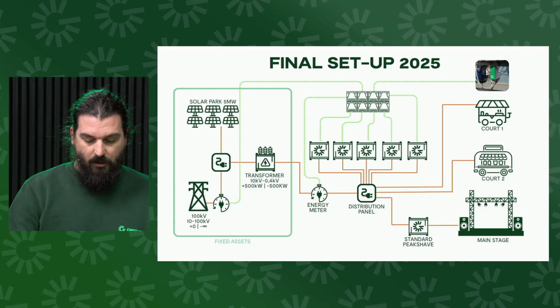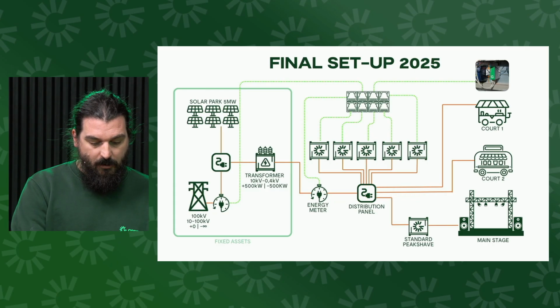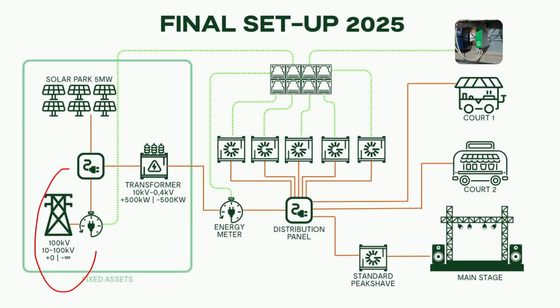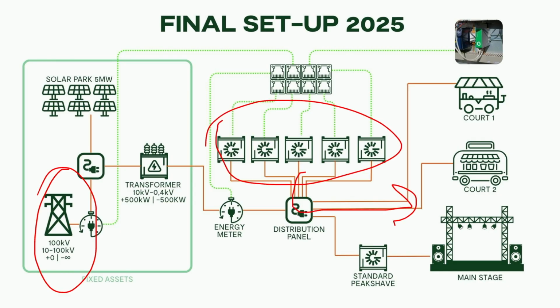And when the solar goes away, the most conservative limit is zero from the grid. So that means these batteries will be discharging into the load and the peak shaver for the main stage, because the peak shaver at that point in time is just a part of the load.